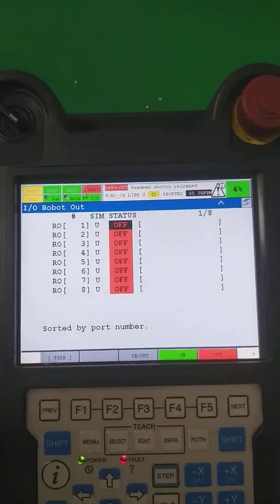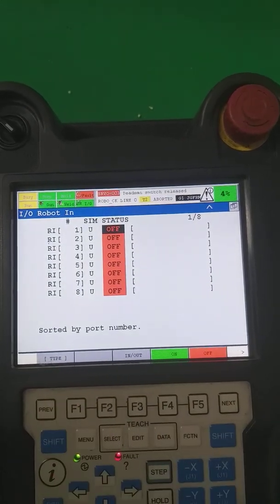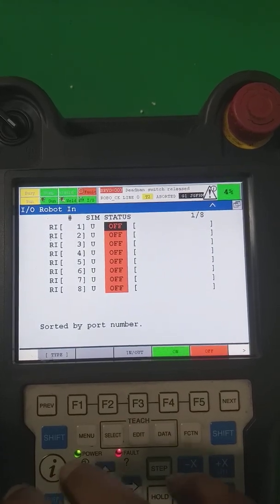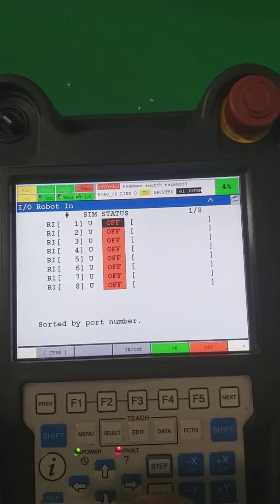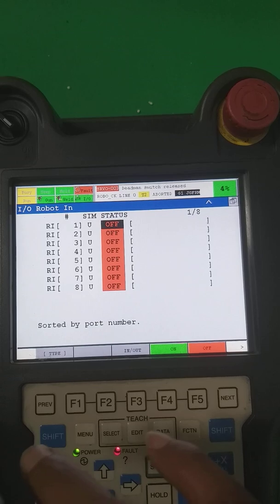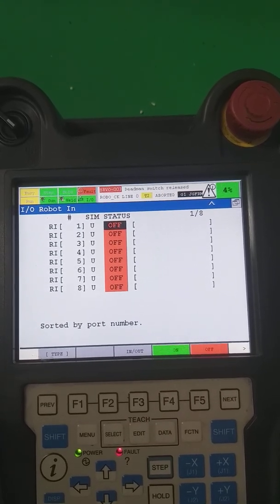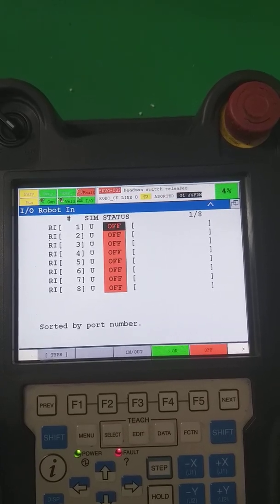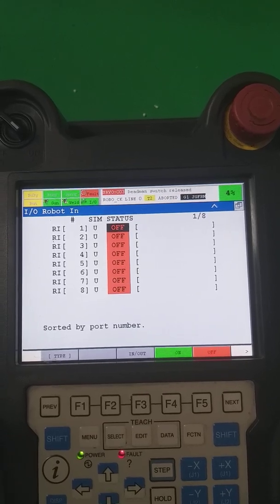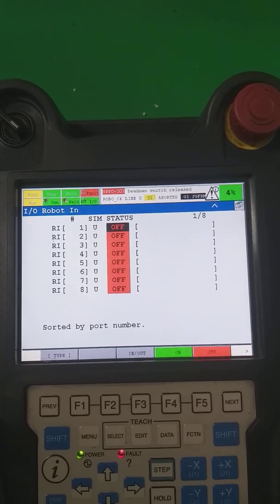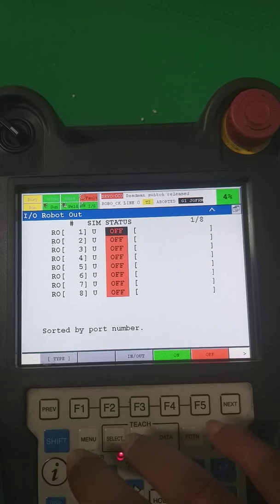The eighth type is robot I/O. These are called RO (robot output) and RI (robot input). These are the input outputs provided by the FANUC maker company for use with end effectors. Generally, if we have a gripper or anything mounted on the tool, we use these robot input/outputs. With these eight inputs and eight outputs, you can also program small applications like gripper handling without needing a PLC. However, it is limited to only eight inputs and eight outputs.